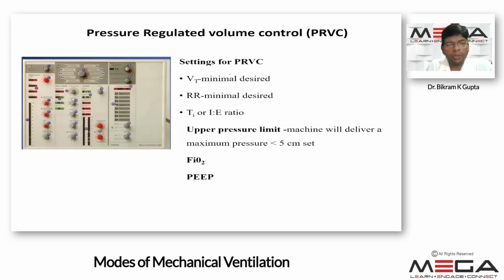So for this, we have to set the following parameters in the PRVC mode. Minimum tidal volume we have to set, minimum respiratory rate as well, then TI or inspiratory expiratory ratio, and upper pressure limit. The machine will deliver a maximum pressure less than 5 centimeters of the set value. We have to keep the FiO2 to maintain the SpO2 level, and then PEEP as well.